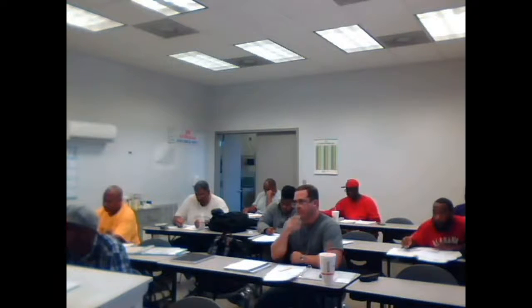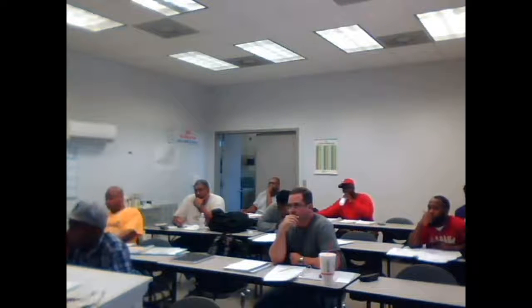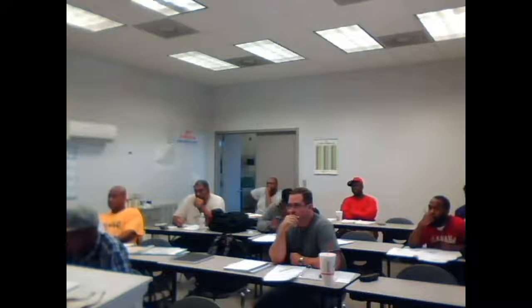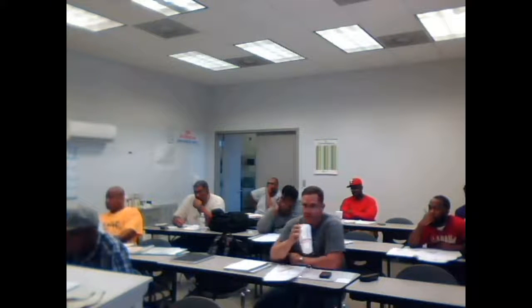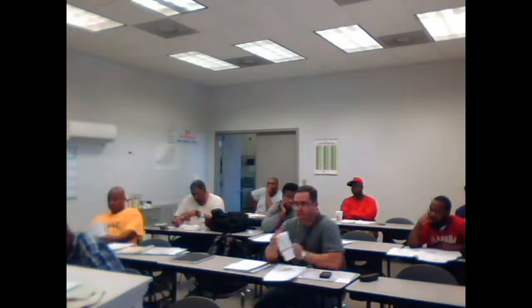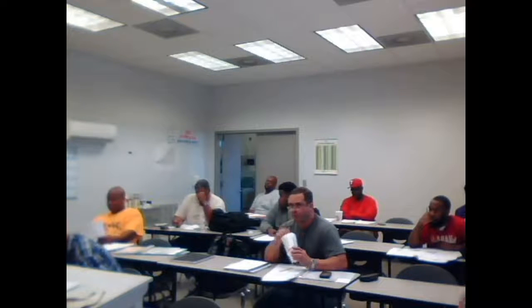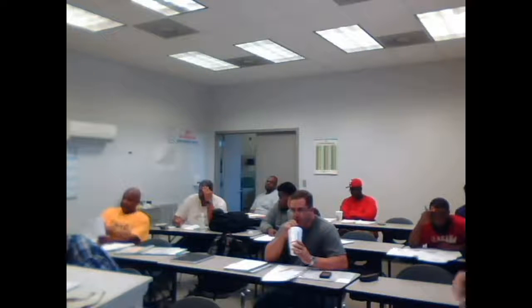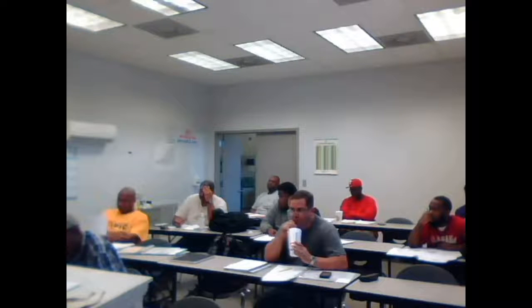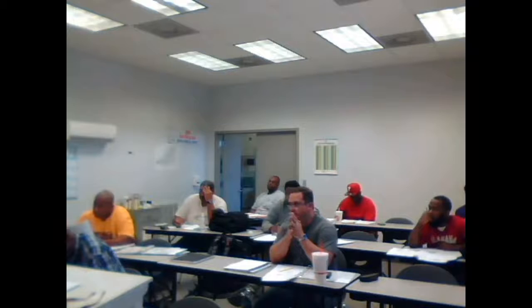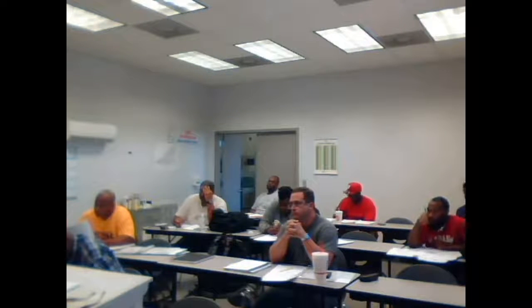After this diagram here, y'all, I'm not going to put common, run and start on the blower motor anymore. Because I think most of y'all saw from the lab, if they don't expect you to do common, run and start, they're going to give you 2 wires for the capacitor. And you simply bring in a line and a speed. So we'll switch over. That's why this instruction is a little vague here. But I like to start it off showing that it's the exact same motor. This probably would have looked better if I had renamed these. Let me rename these. Run, start. So we feed over to run, through the capacitor to start, okay?